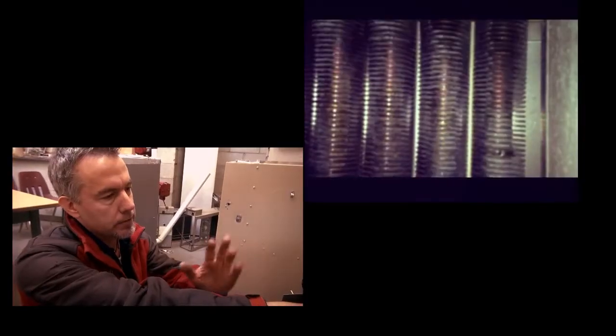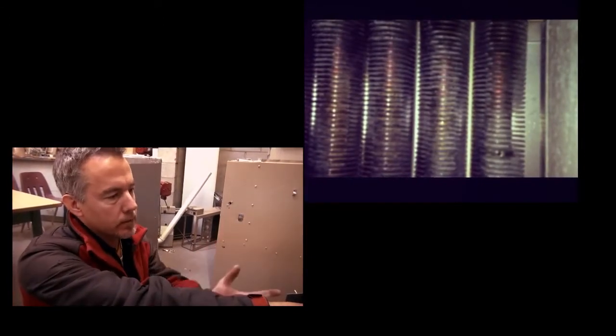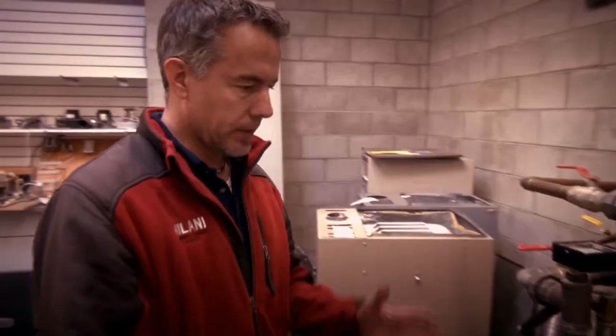If the spaces in between those fins get plugged up, the combustion products will have nowhere to go except spill out of this hole here and into your room. There are reasons why that happens. Some boilers have very tight heat exchangers where the spaces in between them are small, so they can plug up much easier.